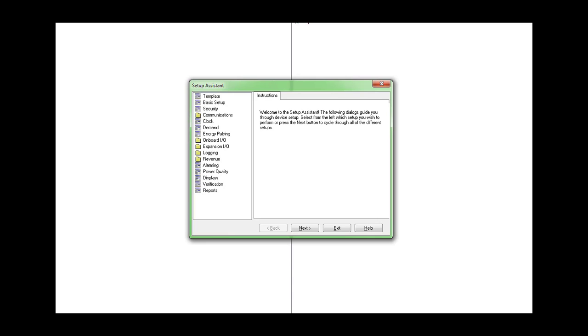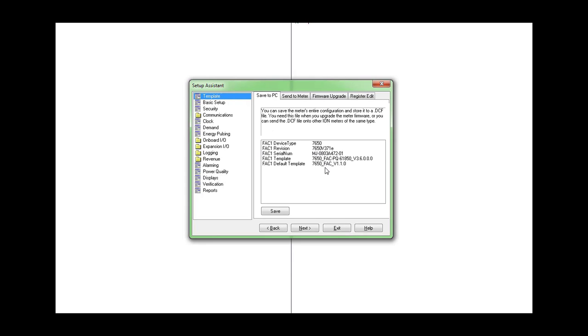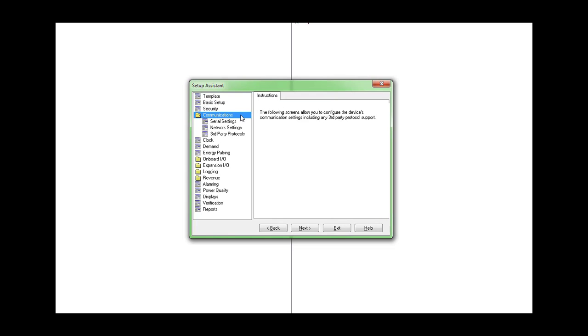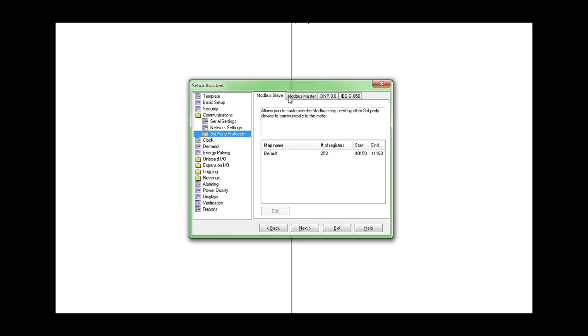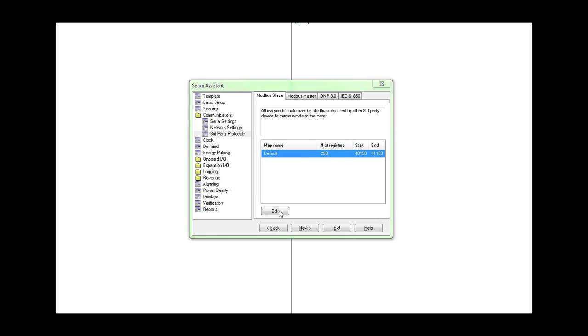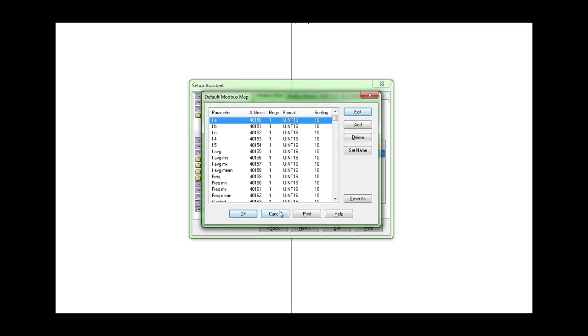Once we can see the setup assistant, we need to check the serial number and the reference of the meter in order to confirm that we are connected to the correct meter. Next, we click on the Communication tab, the fourth on the left side, and then look for the third-party protocols tab, which is the third one in the folder. We can see that there are 4 more tabs on the right side, but we are only interested in Modbus slave, the first one. The idea is to click on Edit in order to start modifying our Modbus register map. The meter password usually is 0 unless somebody has changed it before.